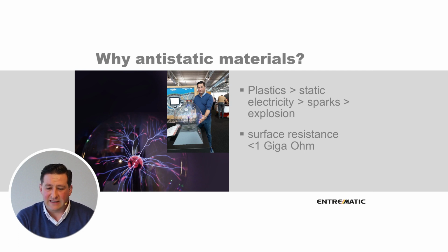Important here is that we stay below 1 gigaohm, where we are much lower with the complete door when all the tests are done. But this is also a magic number: 1 gigaohm. Everything below is okay, is accepted.